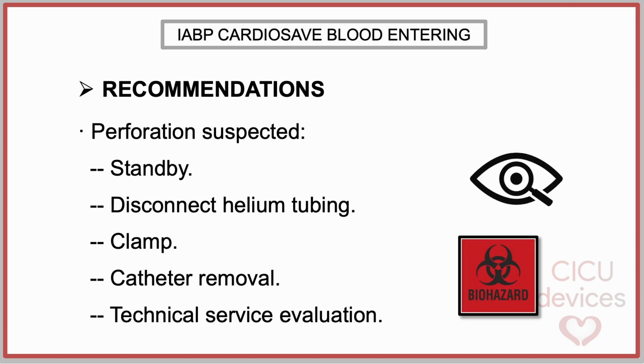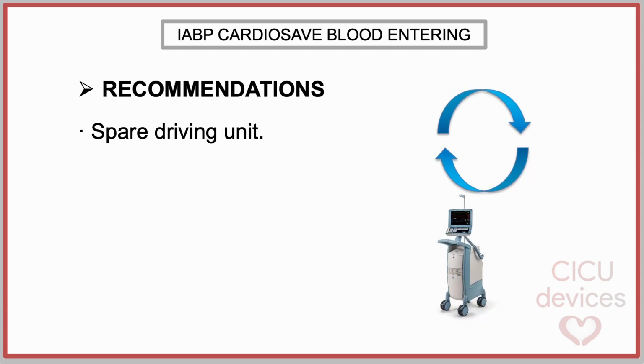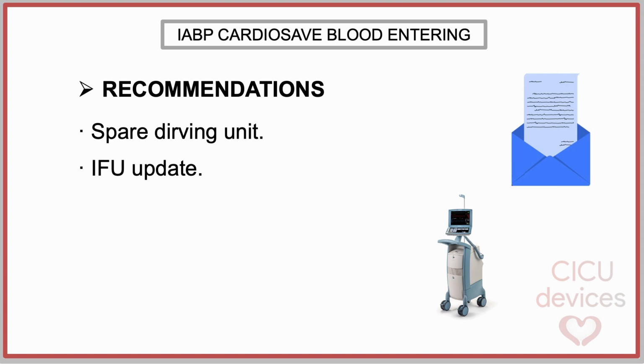Finally, if blood is suspected to have entered the driving unit, the console must be taken out of service until evaluated by the technical service department to determine whether replacement of any potentially contaminated components is required. The company further recommends that a spare driving unit be readily available whenever a patient is receiving IABP support to allow immediate replacement in the event that blood enters the console. Finally, Getinge is updating the instructions for use to include these new clinical considerations.